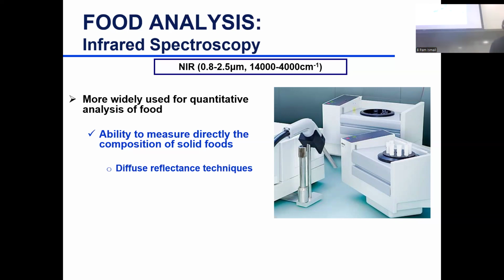And also it is calibrated with standards that have different concentrations. So they can have flours with different amounts of bran in them. So naturally they will have different compositional components, and they will calibrate the NIR. And then it's very easy. You just have to make sure that it's a homogeneous sample put into the sample cup, and then you measure by IR, and it's almost instantaneous, giving you the concentration of fat, ash, protein, etc.